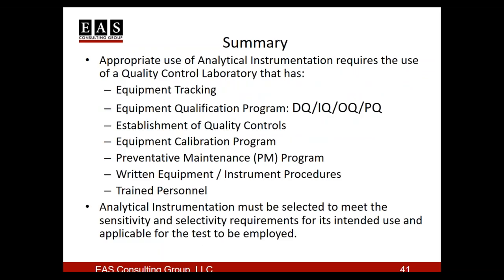In summary, you have to use the appropriate type of analytical instrumentation in your quality control lab. You have to make sure that laboratory is appropriately tracking that equipment, that they've qualified it with a DQ, IQ, OQ, PQ before use, and established quality controls to ensure the equipment meets its accuracy and precision requirements. It's been calibrated before first use and at the necessary frequency, appropriately maintained, and there are SOPs dictating how all of that happens and how the instrument is utilized.